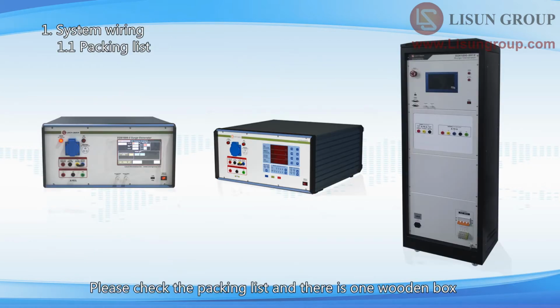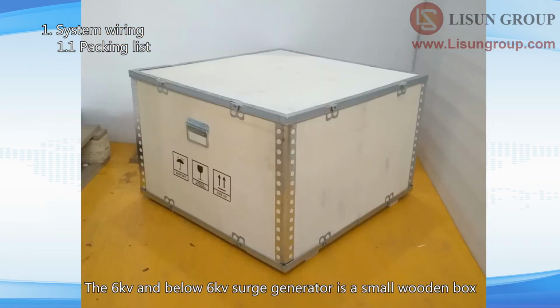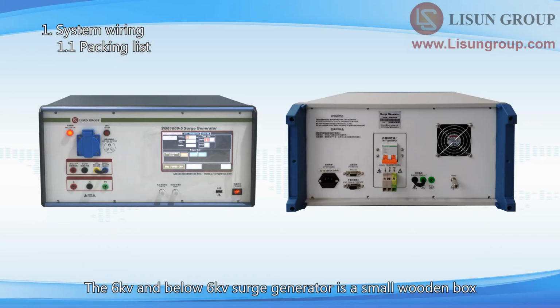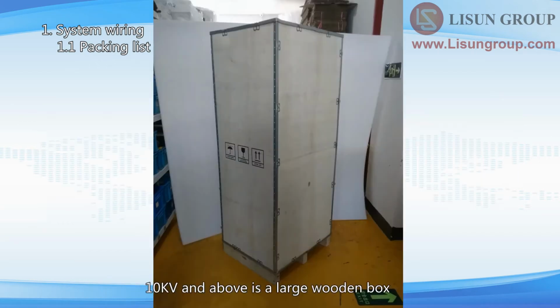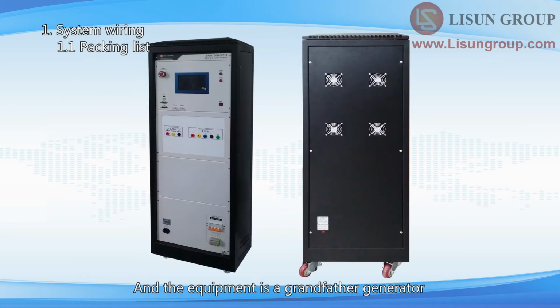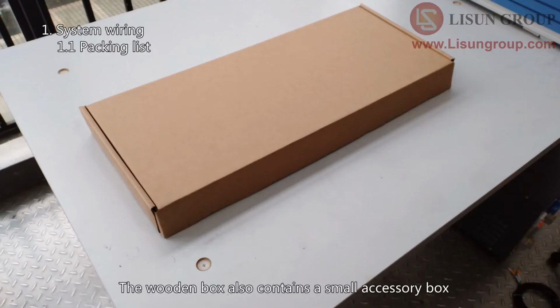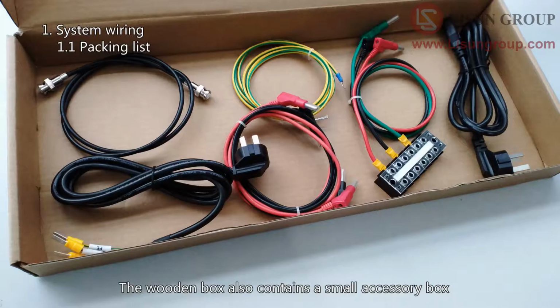Please check the packing list, and there is one wooden box. The 6 kV and below 6 kV surge generator is in a small wooden box, and the equipment is a small desktop surge generator. 10 kV and above is in a large wooden box, and the equipment is a floor-standing generator. The wooden box also contains a small accessory box.